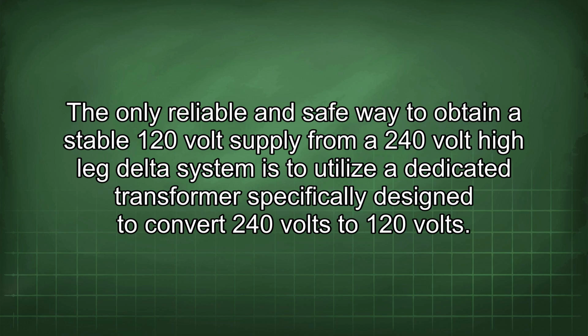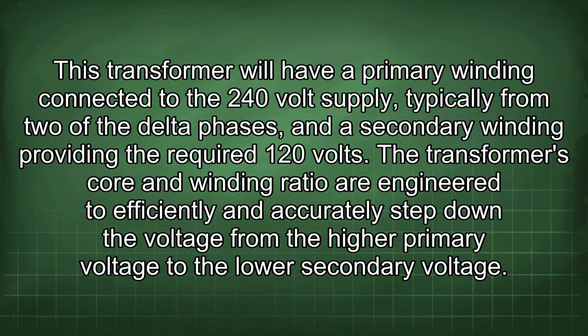The only reliable and safe way to obtain a stable 120 volt supply from a 240 volt high-leg delta system is to utilize a dedicated transformer specifically designed to convert 240 volts to 120 volts. This transformer will have a primary winding connected to the 240 volt supply, typically from two of the delta phases, and a secondary winding providing the required 120 volts. The transformer's core and winding ratio are engineered to efficiently and accurately step down the voltage from the high primary voltage to the lower secondary voltage.